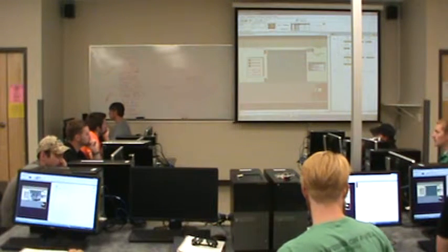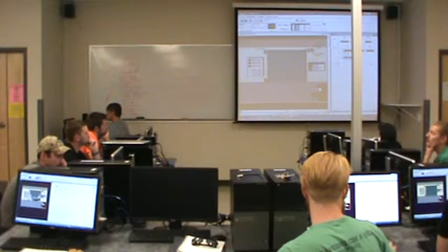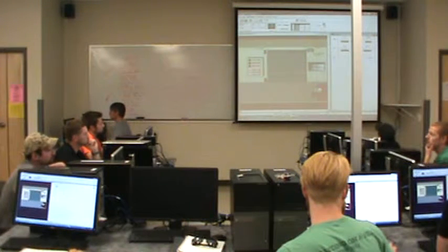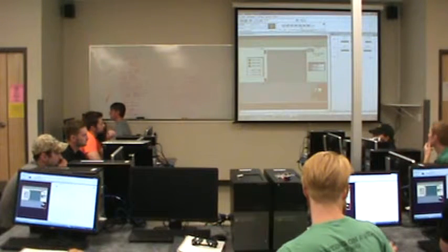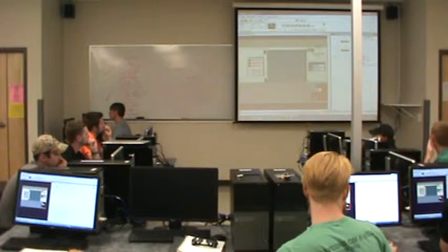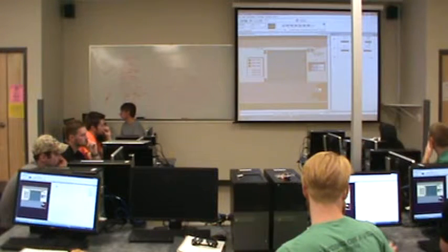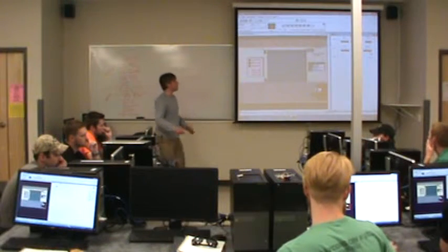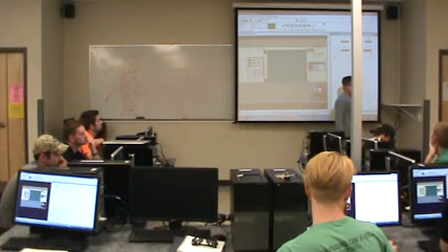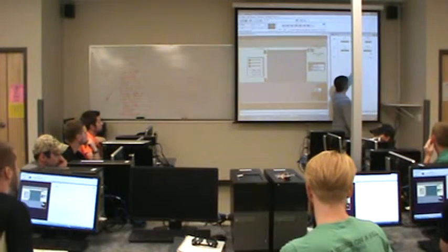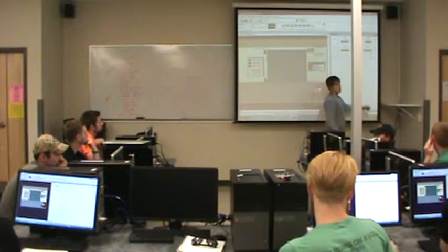We will program, get rid of this branch around stuff. And instead of using the motor up and motor down, just straightforward output energize commands, I can use the so-called output latch and output unlatch commands. So I can latch the motor up, changing it to that, and latch motor down. Now what will happen is it will be self-sealing. In other words, as soon as it gets a true value, then it will just stay on. Okay? And it doesn't matter what happens on the rung preceding it, it will simply stay on.